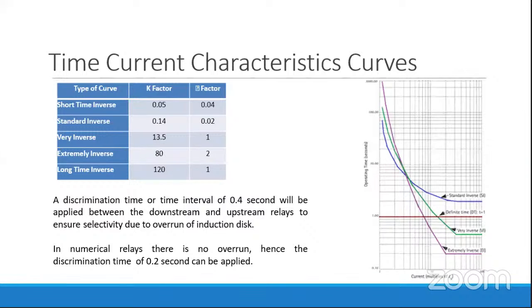Nowadays, in numerical relays there is no disk, therefore there is no overrun, and hence we can reduce the time of operation in order to isolate the faulty section as soon as possible, so that the healthy portion does not get affected. Therefore, the time discrimination has been reduced to 0.2 seconds, that is 200 milliseconds, which can be applied between two curves. The time discrimination applied between two curves should be 0.2 seconds.